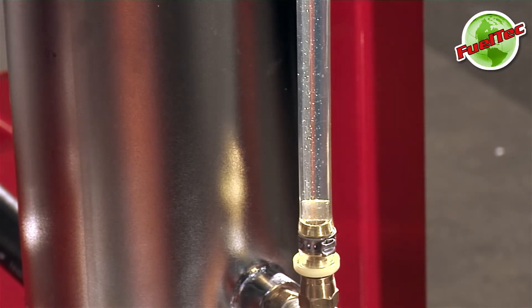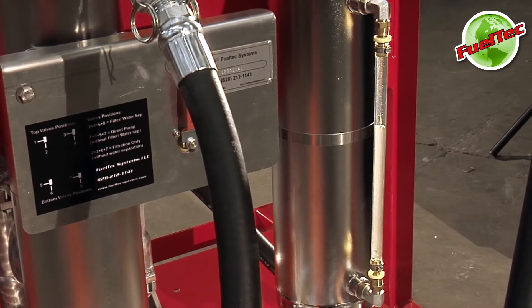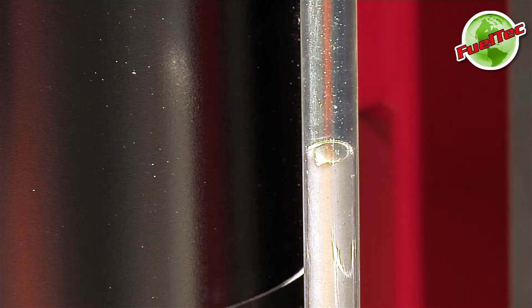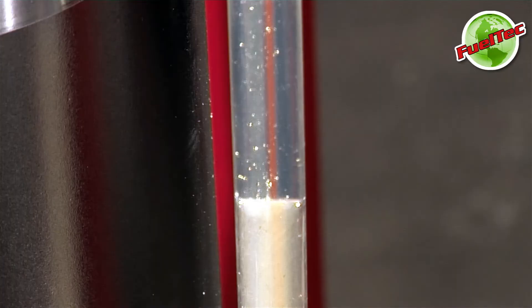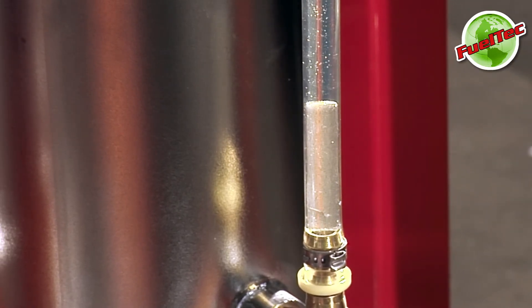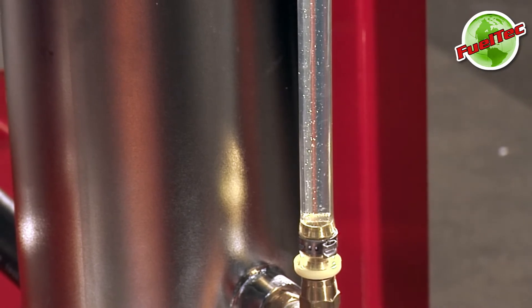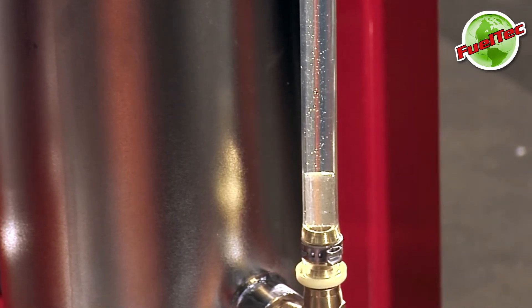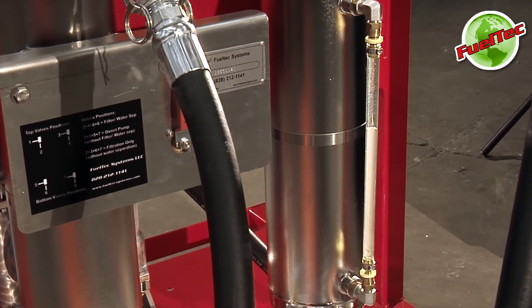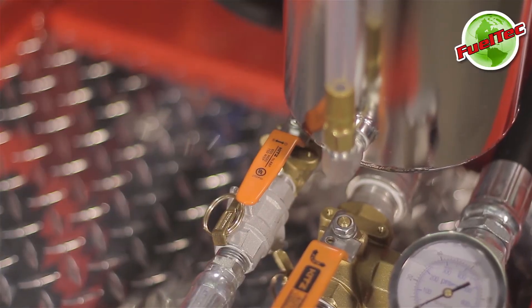The separated water level will continue to rise as it is being separated from the fuel. Repeat the draining steps until all of the water has been removed from the fuel. You will know the filtering is complete when the water level stops rising in the sight tube. When the separated water stops rising, drain the separator completely.